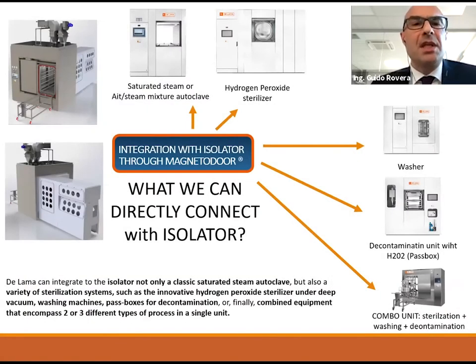Considering that De Lama is able to manufacture, as you might see here starting from the top down to the right, saturated steam or air steam mixture autoclaves, hydrogen peroxide sterilizers. When I say sterilizer, I mean log 6 reduction in high vacuum, meaning it's a real sterilization for everything but liquid loads. Washers, decontamination units with hydrogen peroxide, or combined units, which combine one of the techniques I just shown to you into one unit only, meaning we can sterilize, wash, and decontaminate in the very same equipment.